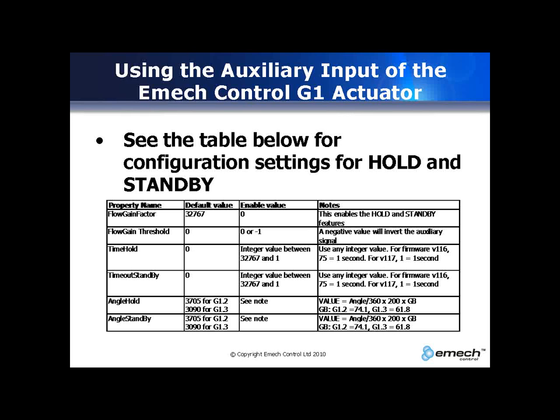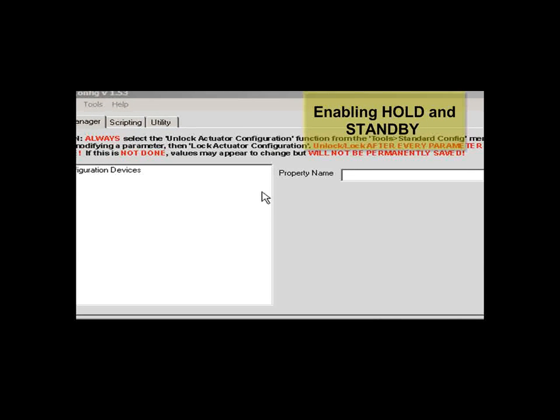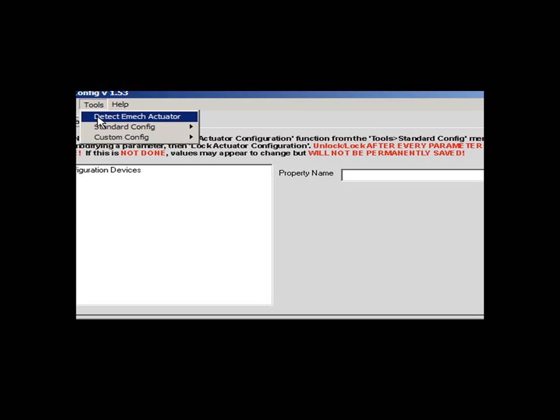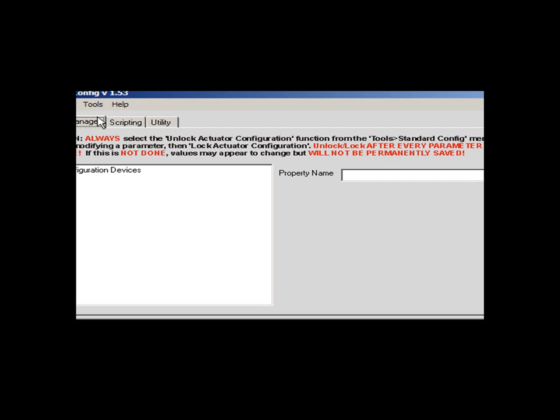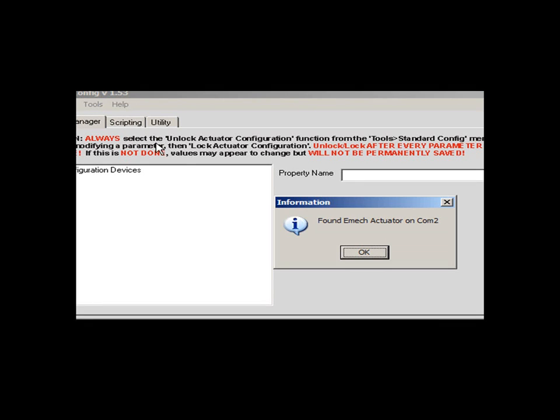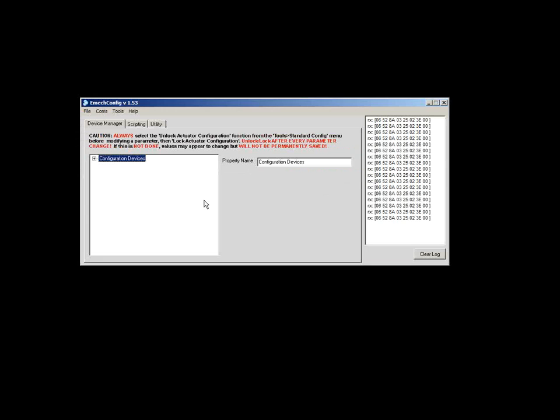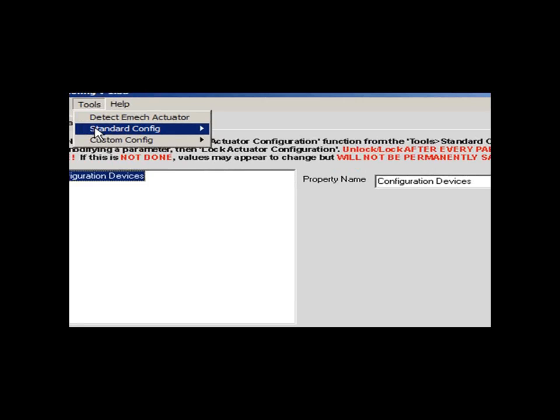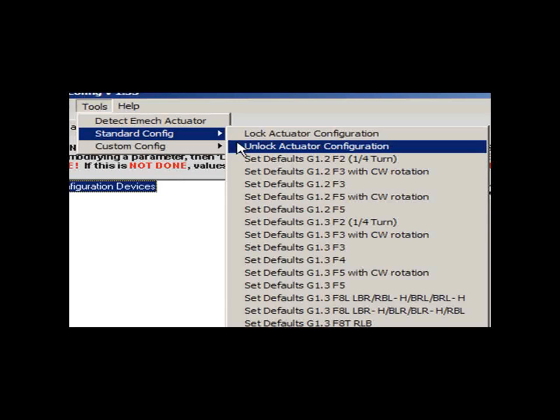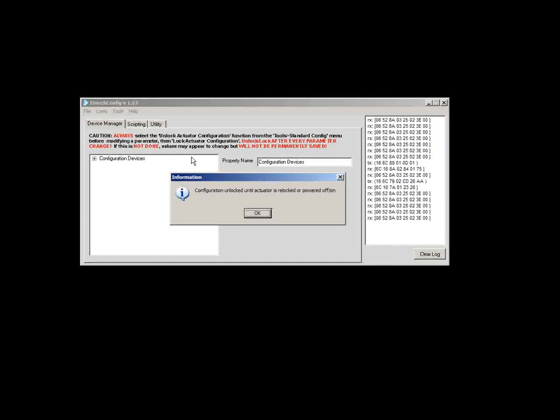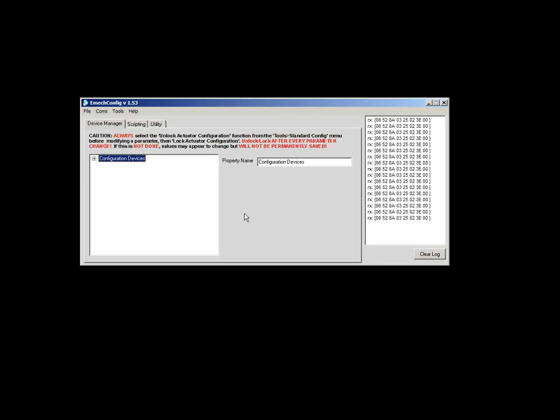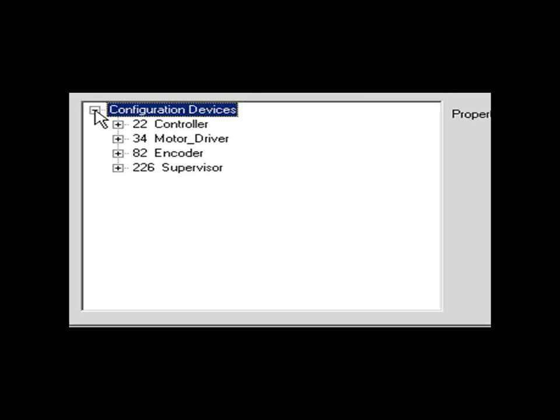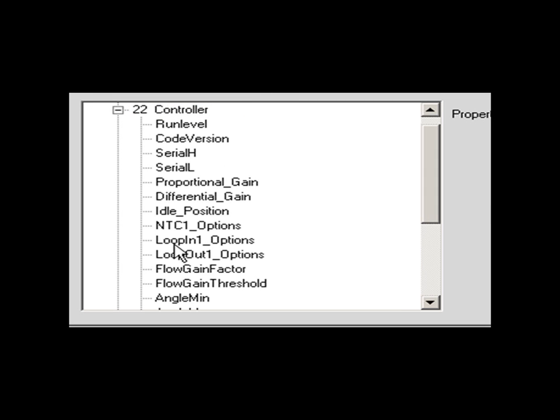The table shows valid configuration settings to be used when hold and standby features are enabled in the actuator. First step is to establish communications with the actuator by clicking on Tools and Detect Emech Actuator. After the actuator is detected, click on Tools, select Standard Config, then select Unlock Actuator Configuration. Next, select Configuration Devices. Move down and select 22 controller.